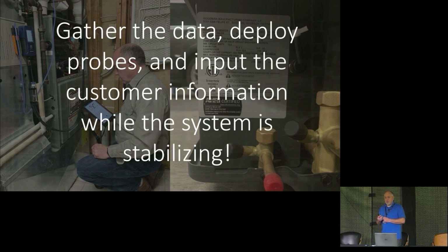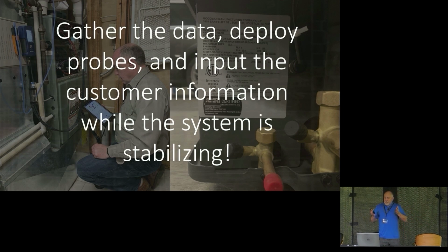We get other contractors, and this is where I was talking to somebody about this particular market in Florida, where they think it just takes too much time, right? Because their mentality has been, they go out there, Mrs. Jones has got no cooling. They walk out, they pop the cover off the condensing unit. They go, oh, bad capacitor, easy $300. Take the cap out, put the new cap in, push the disconnect back in, calling the boss for the next call. Literally 5 minutes, right?